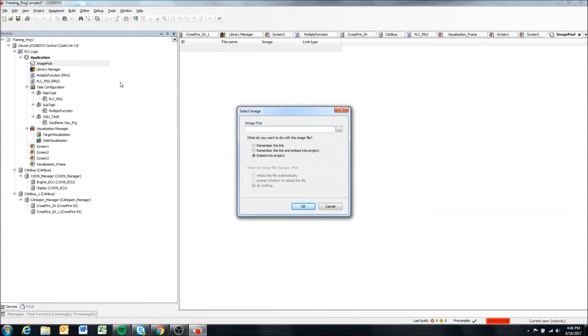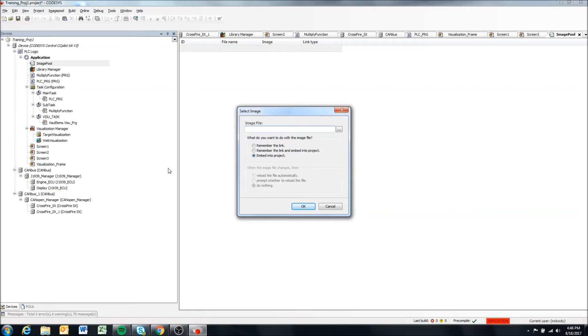So when you put the program or this Codesys application onto the display and it tries to load the image, it's going to say, okay, my image is in my home folder. And if the path to that image isn't the same on this computer as on your display, it's not going to be able to find the image itself. So the easiest solution to this is just embedding it into the project.